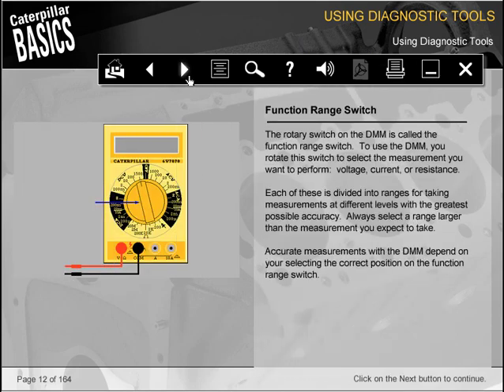The rotary switch on the DMM is called the function range switch. To use the DMM, you rotate this switch to select the measurement you want to perform: voltage, current, or resistance. Each of these is divided into ranges for taking measurements at different levels with the greatest possible accuracy. Always select a range larger than the measurement you expect to take. Accurate measurements with the DMM depend on your selecting the correct position on the function range switch.